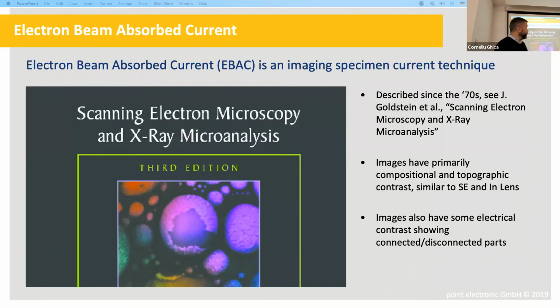And perhaps the first technique, the most fundamental one that comes into this, and it's not a direct technique for electrical analysis, but it's a very good foundation, would be electron beam absorbed current. And it is exactly what it says. It's a current technique. So we measure the current absorbed into the sample. And that's the current that's due to the electron beam. So it's not light induced or thermally induced. Specifically, we mean the current induced by the electron beam.